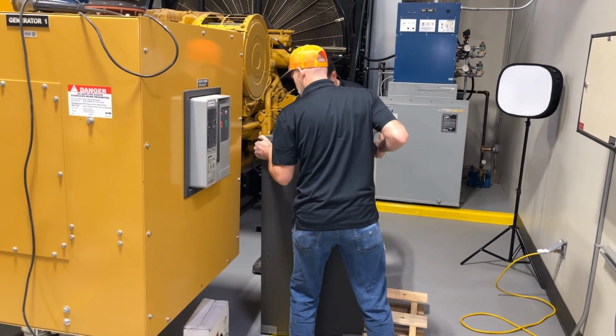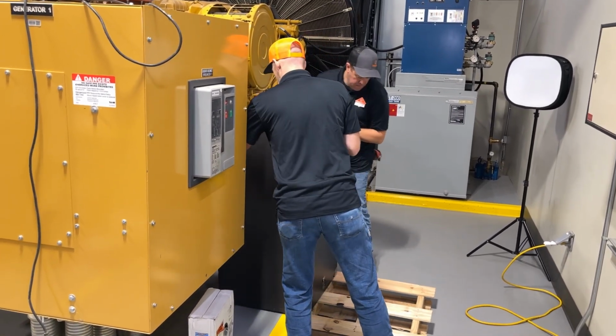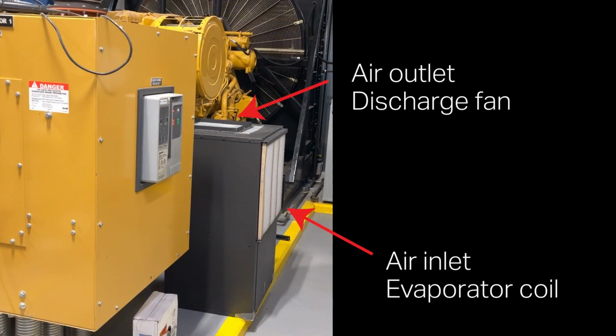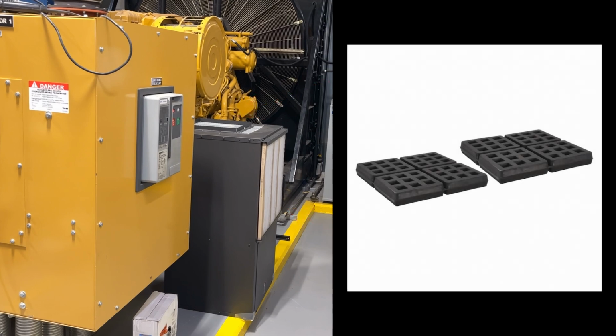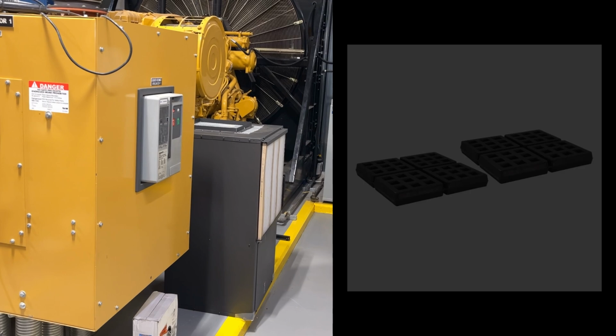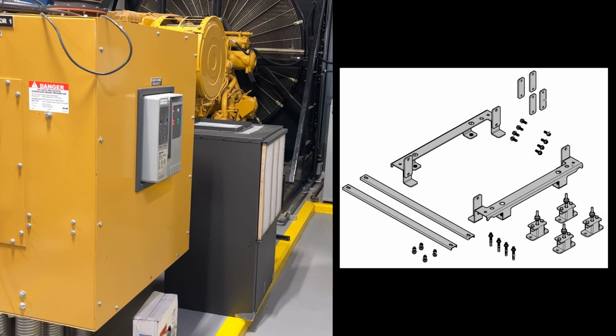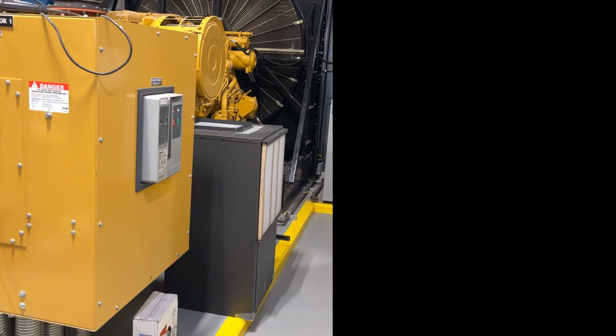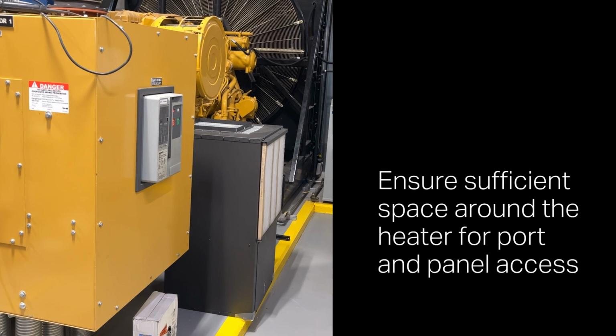Position the heat pump on a flat level surface in the predetermined location near the generator. Allow for unrestricted airflow around the unit for proper air inlet at the evaporator and air outlet from the discharge fan. Place rubber isolation pads under the heater base to prevent condensation from collecting under the unit and to minimize vibration when the generator runs. For regions prone to seismic activity, an optional seismic mounting kit is available from Hotstart. Allow suitable access to service panels and ports when determining the mounting location.